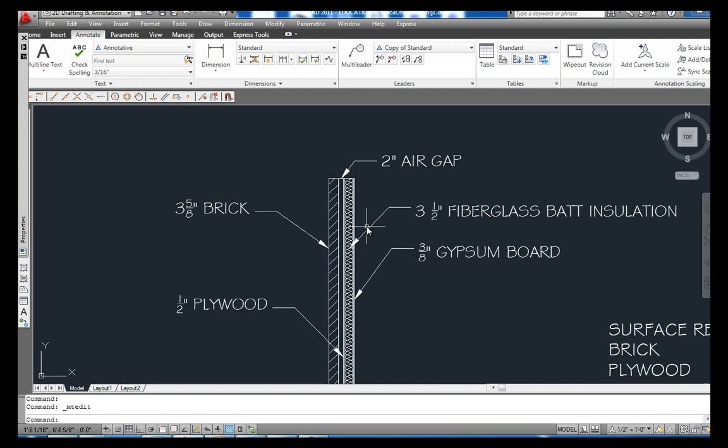So with that in mind, let's go ahead and figure up some numbers. First thing that you need, if you're trying to figure R-value, is that always on each side, exterior and interior, you've got what's called surface resistance. There's a thin invisible layer of air that floats around that wall. You'll have one on the inside and one on the outside. It acts like a shield and it does have value as far as resisting change in temperature. The inside is estimated to be 0.7 R-value. That invisible little wall of air is 0.7. The exterior is 0.2.